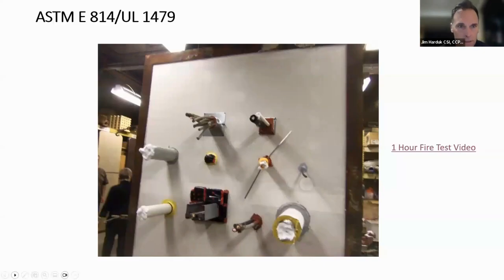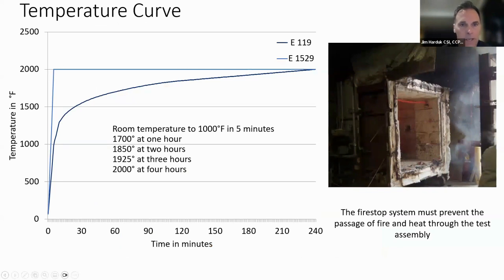All right. So that was a 1 hour test. And so the time temperature curve is basically the temperature that these furnaces are fired at, and this is based on ASTM E119. So you could see a 1 hour test, we're talking about 1700 degrees. 2 hours, it's 1850 degrees. And if we go up to a 4 hour test, we're at 2000 degrees. So we're talking some pretty substantial temperatures here. Next slide.